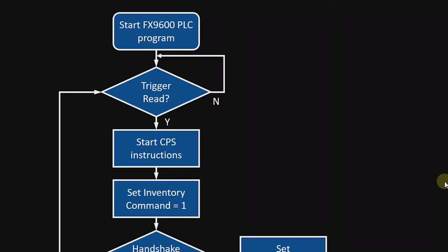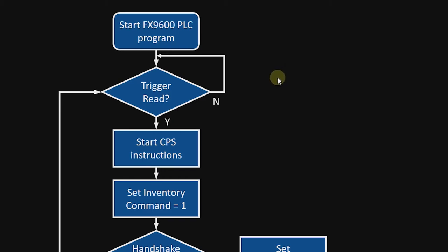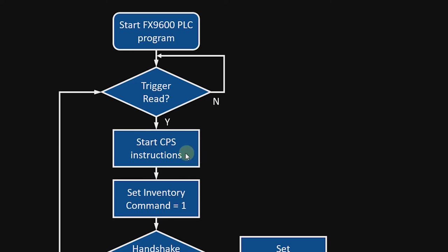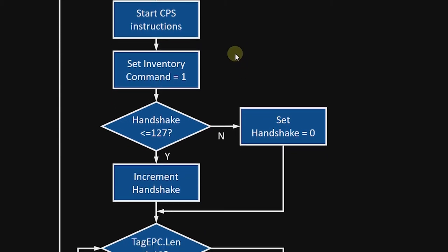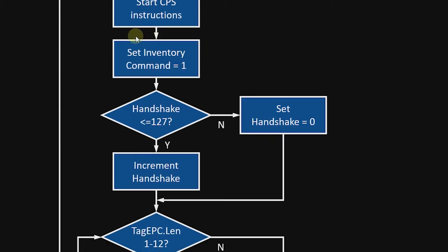Okay, so before we get started on the ladder logic, I wanted to go over the general process flow for how my program is set up. There is the start here where we have the program downloaded into the PLC and it basically waits for something to trigger a read process. When we have that trigger occur, we start this copy synchronous file instruction which is running the entire time because what it will do is allow me to copy any instructions to the reader and receive any results from the reader back into my PLC. I will then need to set the inventory command to one. That's the read setting. I will increment my handshake and that handshake has to be between zero and 127 as far as the value is concerned.